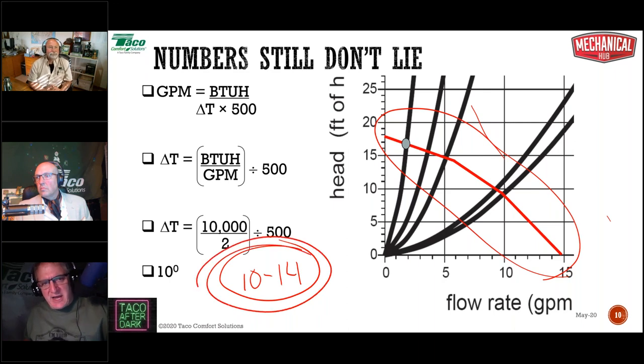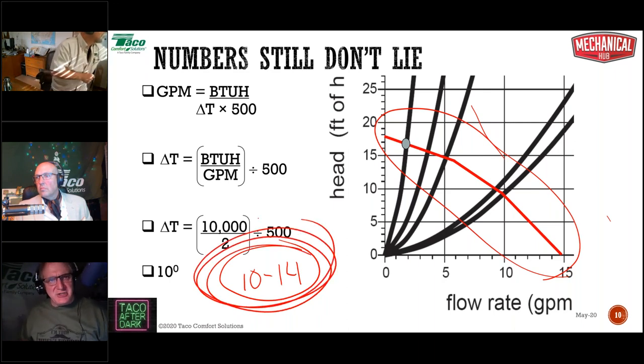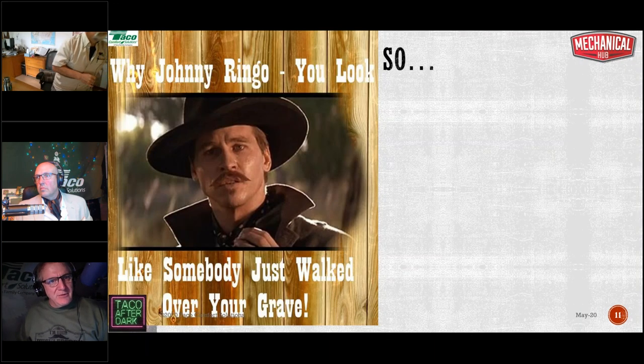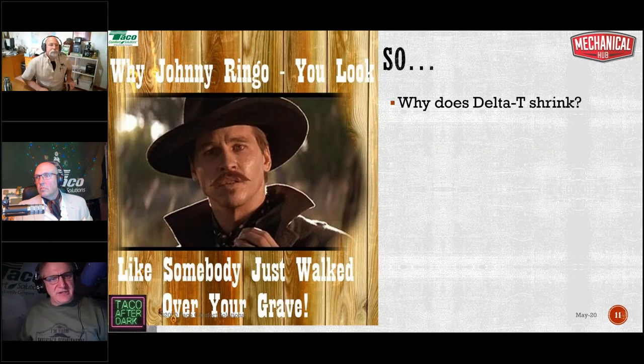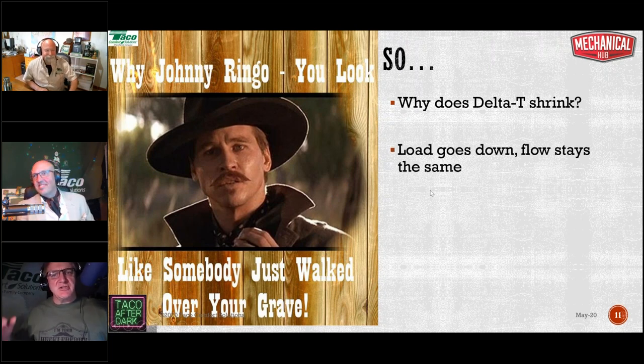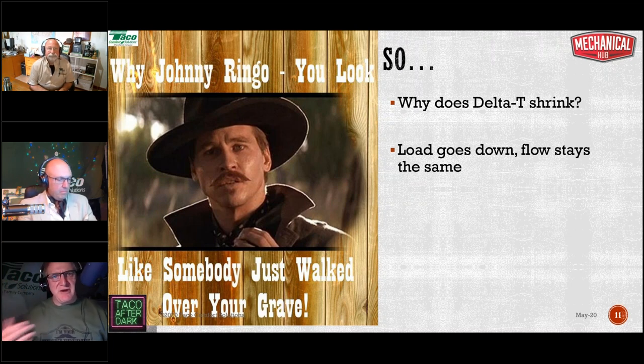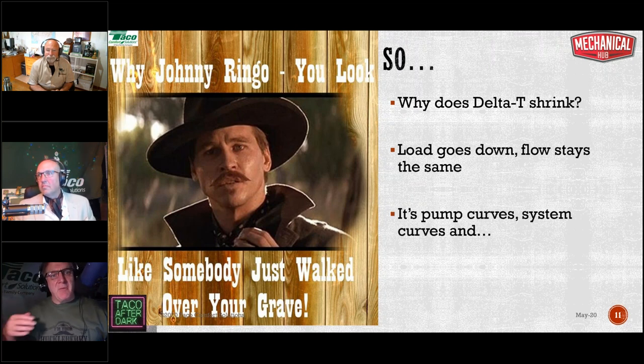However, we cannot ignore that, because what does that lead to, all right? What does that lead to? It looks like somebody just walked over your grave. Why does the delta T shrink? The delta T shrinks because it has to. The load goes down. The flow stays the same. GPM equals BTUH divided by delta T times 500. GPM stays the same. The load fluctuates. The delta T has got to fluctuate along with it. That's only natural. It's the only thing it can do.